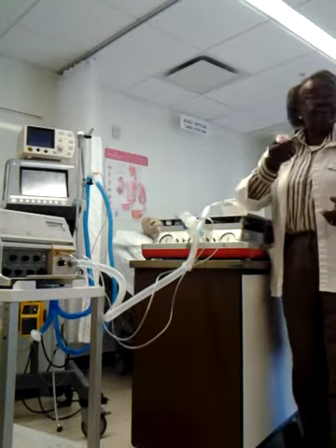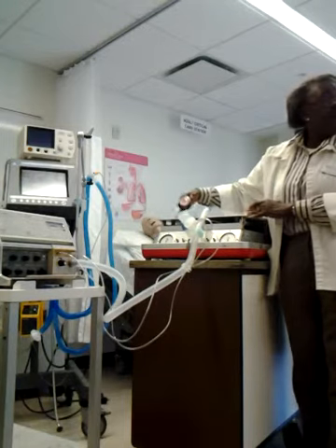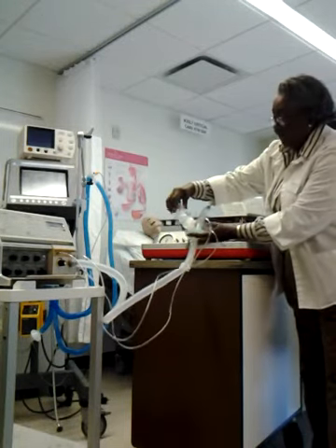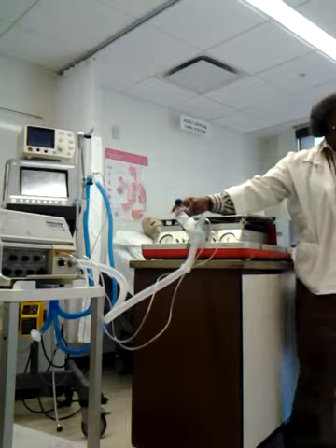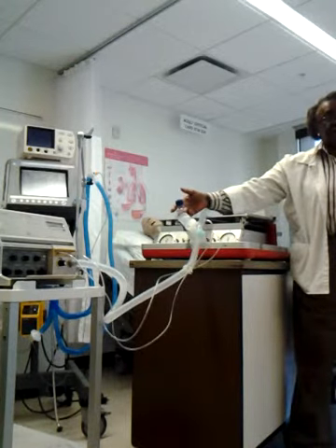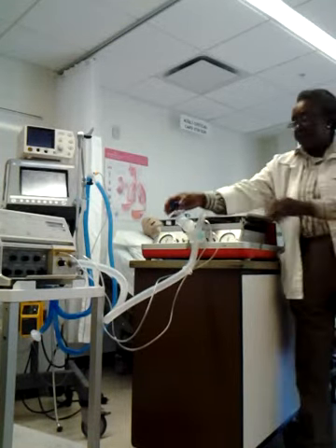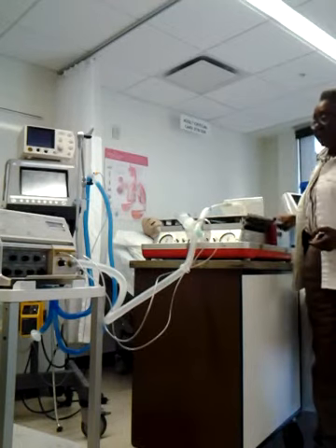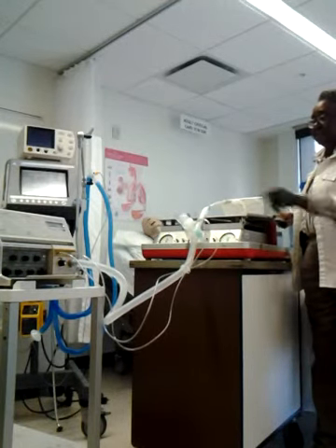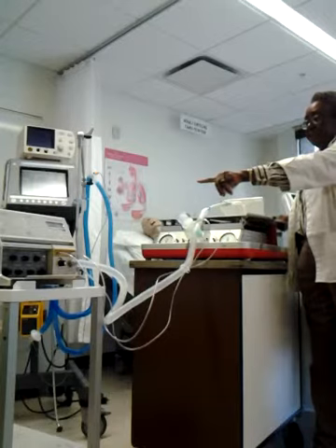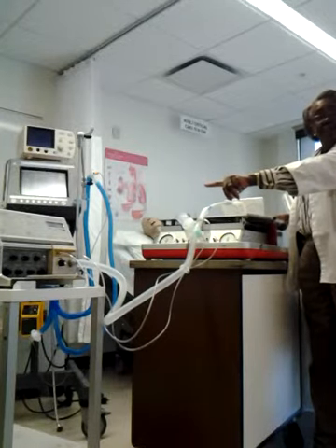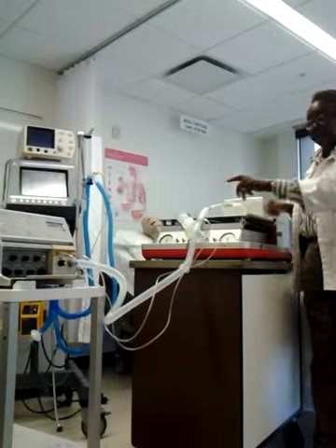Makes sense. So when you're going to put a PEEP valve on, since there's nothing internally that you can set for PEEP, you have to actually put a PEEP valve on the expiratory limb of your circuit. And then that gives you your PEEP. And what I was also showing you before was when the patient is breathing spontaneously, you see the little light come on down here where it says breathing effort? It's telling you that your patient is taking a spontaneous breath.